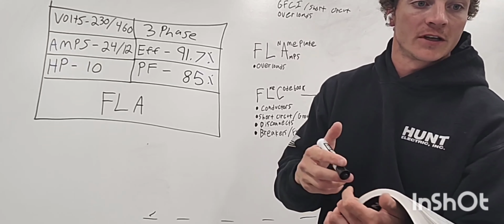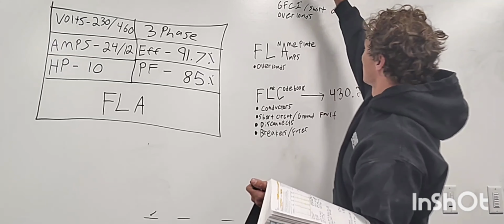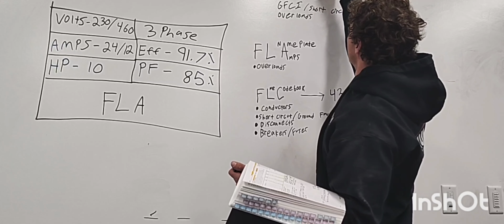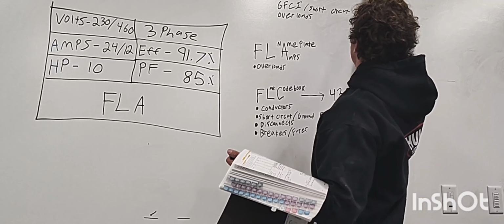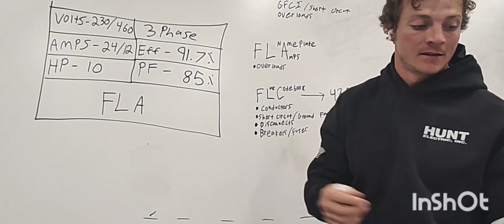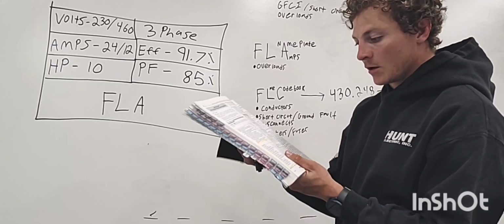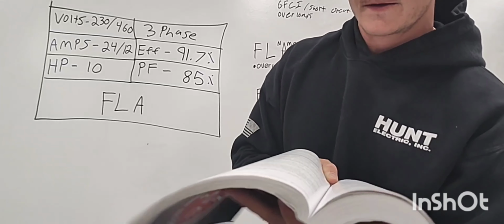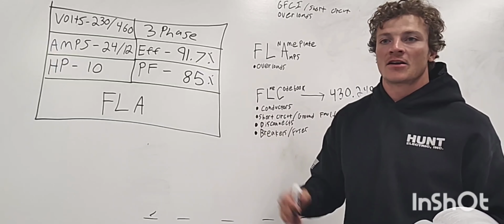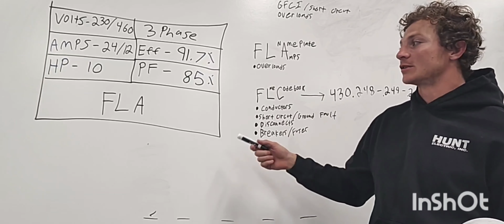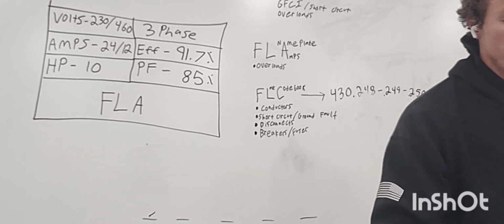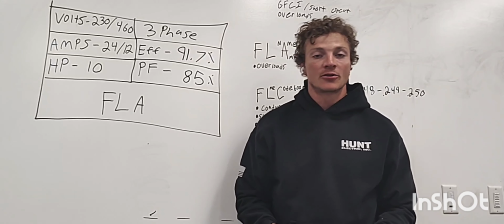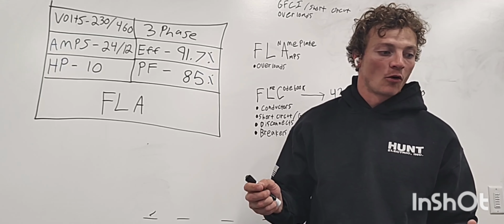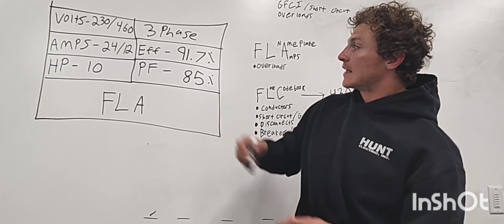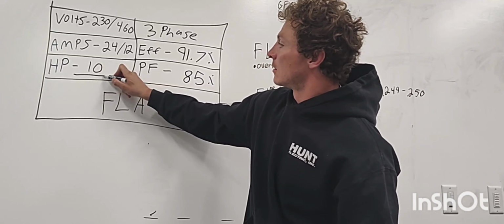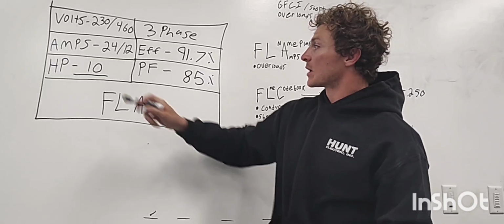Now remember, 430.6A1 is the reference to the FLC. So let's flip to that real quick. So in 430.6A1, I don't know if you can tell, but it's essentially saying when you need to use FLC and when you need to use FLA. So what we're going to do, on page 332 in my year 2020 code book, is the horsepower ratings of each of the motors. We're going to take this number right here, and we're going to plug it into the NEC. So we have 10 horsepower.